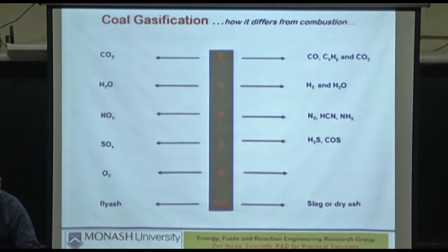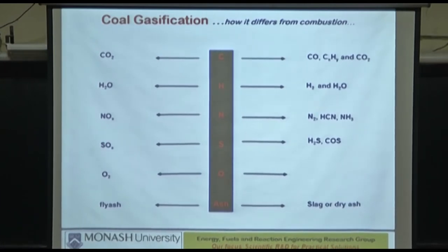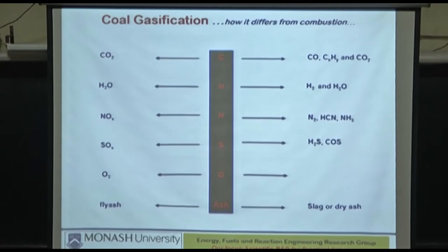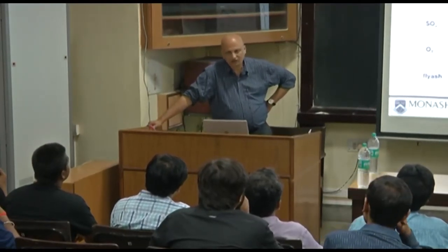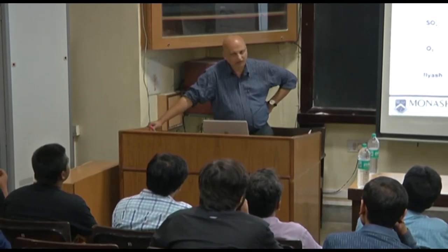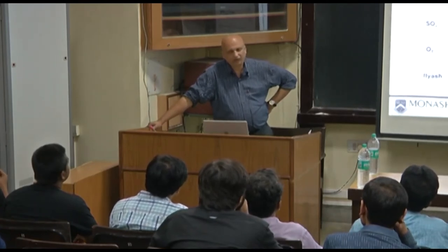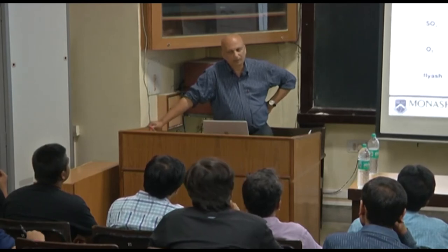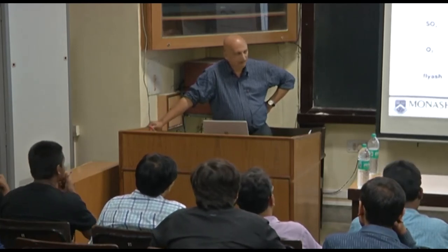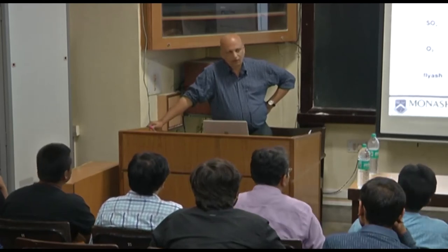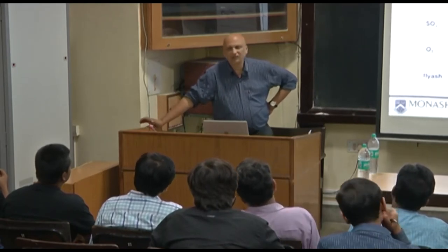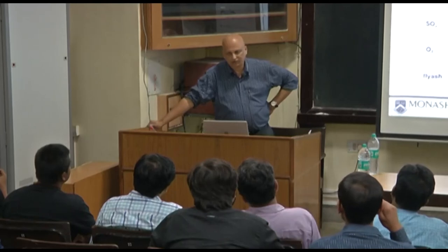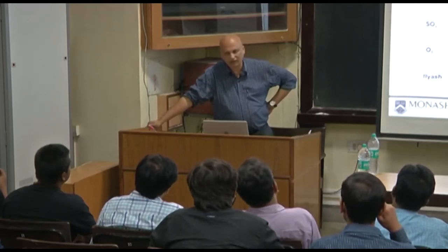In general, in gasification, because you are not supplying air, you are supplying predominantly oxygen, you are avoiding a lot of the nitrogen going into the high temperature environment of the gasifier anyway. So that really keeps the NOx level very, very down. I mean, below the permissible limits, usually. Not usually, always. So it's not correct to say that it's not at all formed, but it is very, very low, below the permissible limits, so that the EPA will not be any factor.